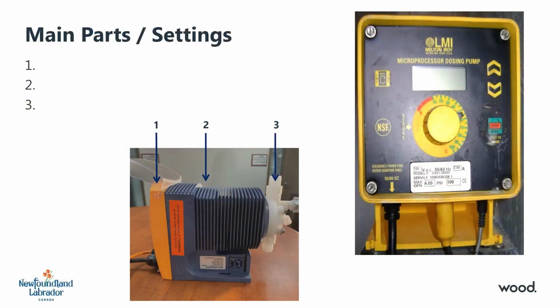Chemical feed pumps are used to inject a precise amount of chemical or other substance into the water. Within your water distribution system, chemical feed pumps are often used to inject chlorine solution into water supplied to the distribution system. A chemical feed pump is made up of the following parts: the system controls, including the display screen, control knobs, and indicator lights where applicable, the drive unit, which houses the operational parts of the pump, and the liquid end, where the suction and discharge valves and lines are connected.